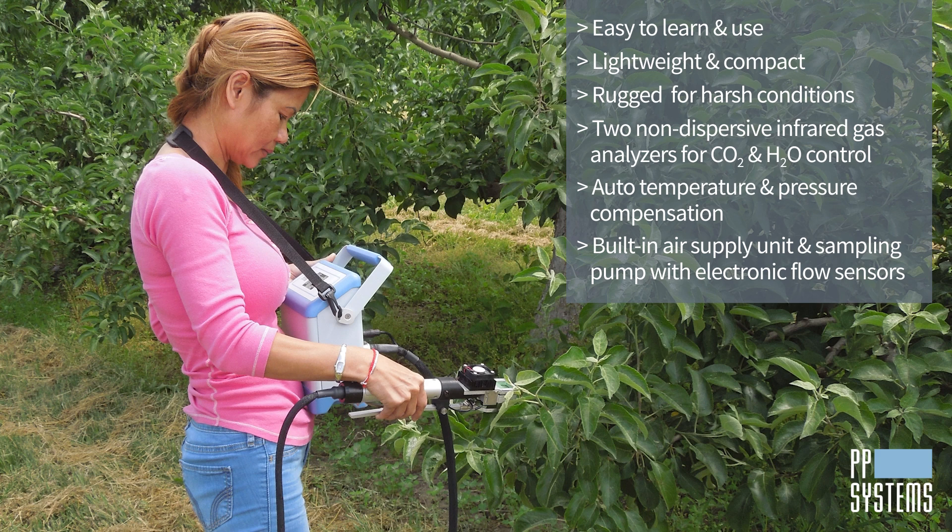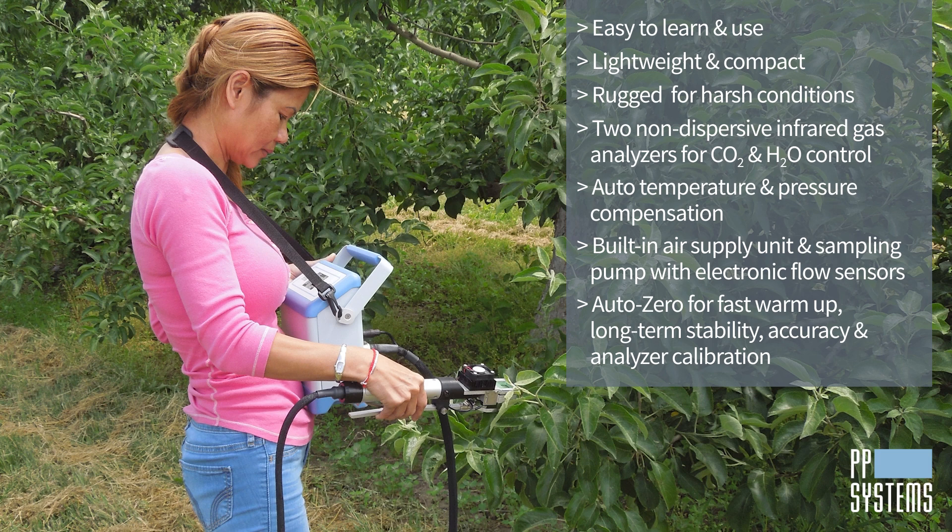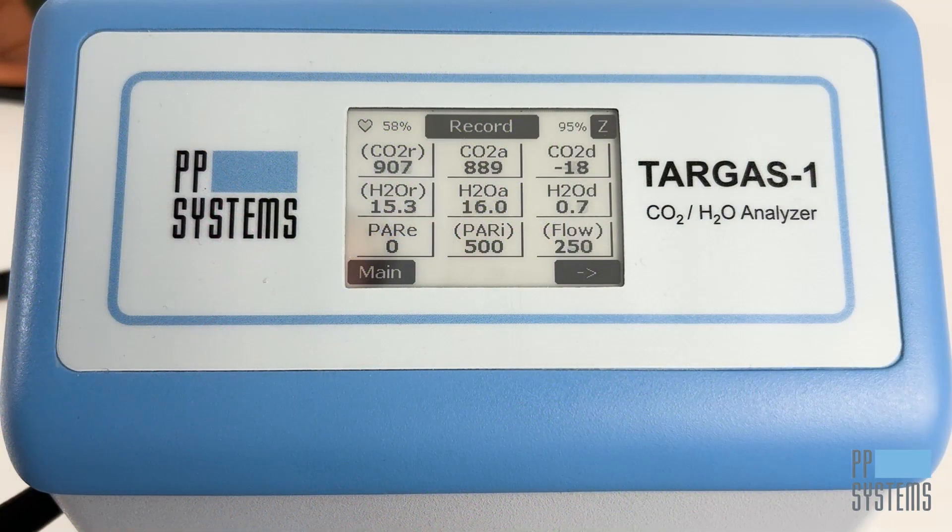Two internal electronic flow sensors provide the utmost accuracy. Our innovative AutoZero technology ensures fast warm-up, long-term stability, accuracy, and analyzer calibration. The TarGAS-1's rechargeable lithium-ion battery provides up to 10 hours of field operation.